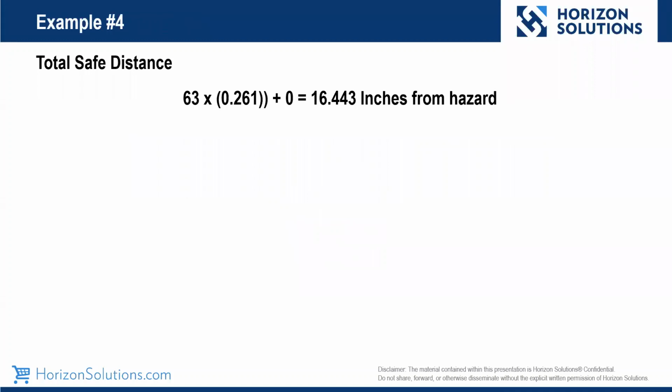Again, I know we're talking a max difference of less than 7.5 inches between the relay solution and this solution. However, 7.5 inches around the entire perimeter of a machine, if you are safeguarding on all sides, will be increasing your footprint by over 1.5 feet in every direction.